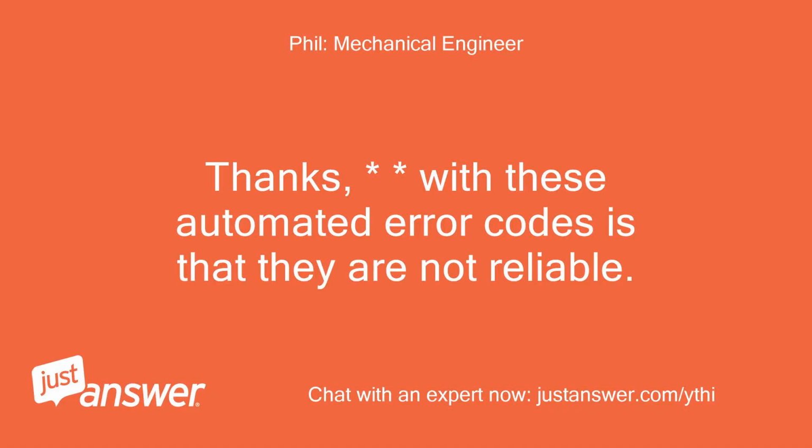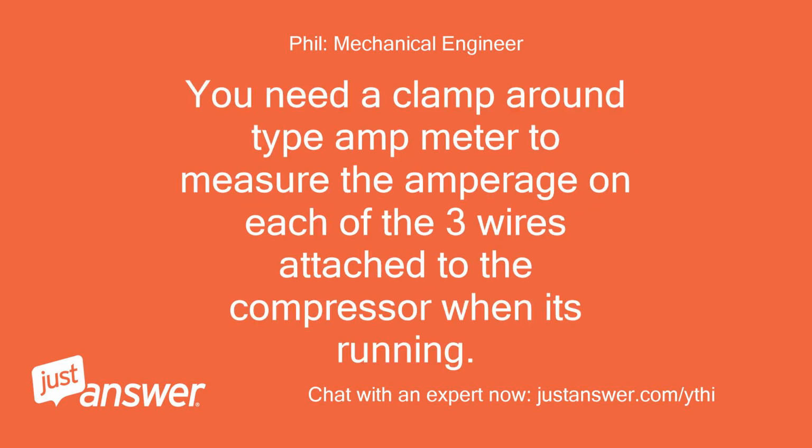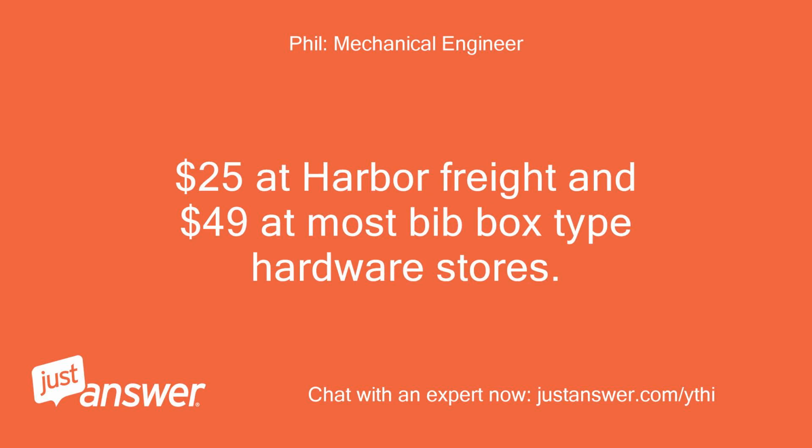Thanks. The problem with these automated error codes is that they are not reliable. They can issue the wrong code if, for instance, the printed circuit board is bad. You need a clamp-around type ammeter to measure the amperage on each of the 3 wires attached to the compressor when it's running. $25 at Harbor Freight and $49 at most big box type hardware stores.